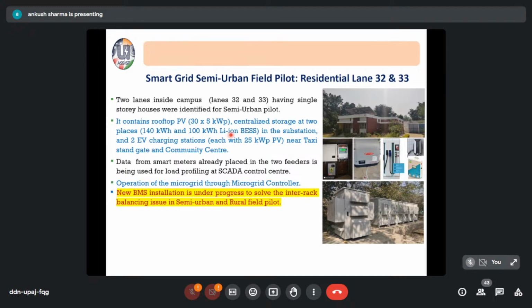We disconnect lane 32 and 33 from the rest of the campus grid and create a local island with these two battery energy storage systems. This hybrid inverter acts as a grid forming inverter, giving voltage reference to the rooftop solar PV systems so that solar power output keeps coming to the local islanded grid. So the limitation of not having solar power output under outage condition is addressed through this islanded operation.